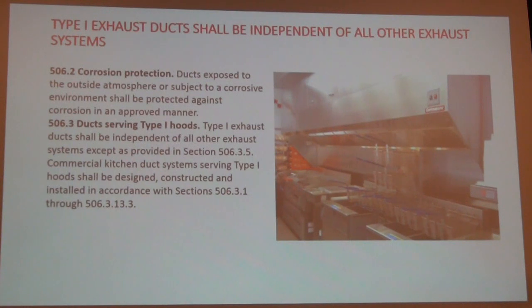Okay, all those restaurants in that food court, originally they submitted plans for one exhaust system for all the restaurants. That's insane. But it is on the same floor, so they could do that. Well, here's the thing, I sent it back to the engineer. I said, okay, how are you gonna design this? If you get one restaurant that needs extra heavy-duty cooking, what parameters can you go by? What are you gonna do? And what if you don't design it enough for all the things? And so they backed off and made it an independent system for each restaurant.